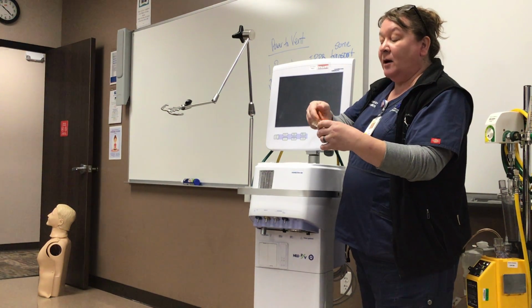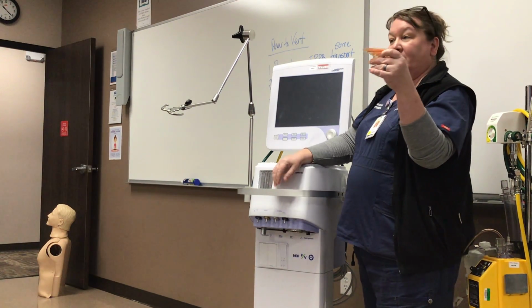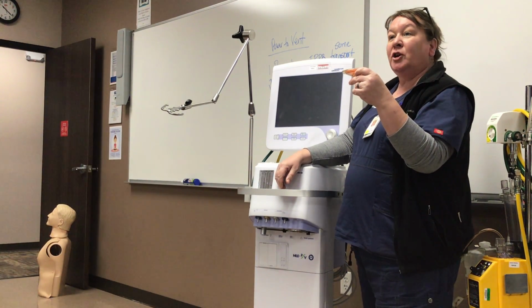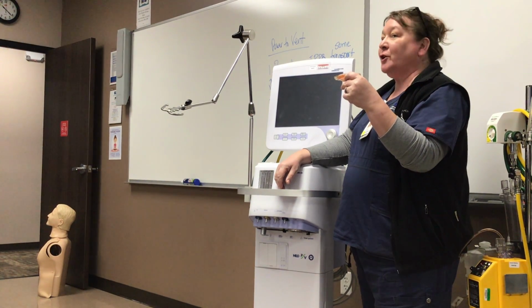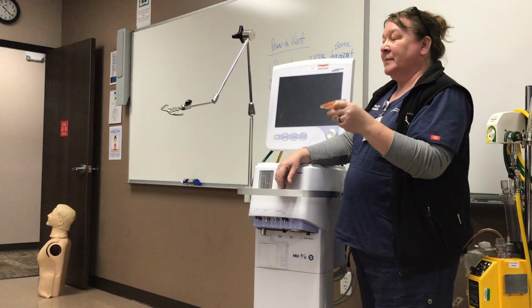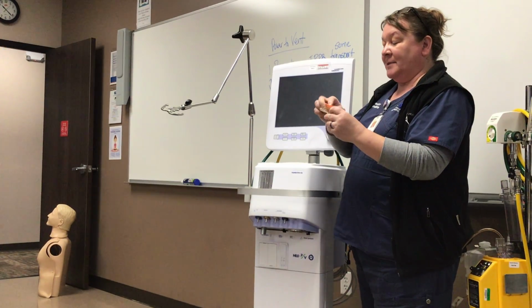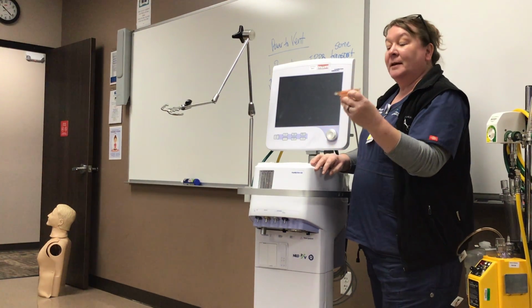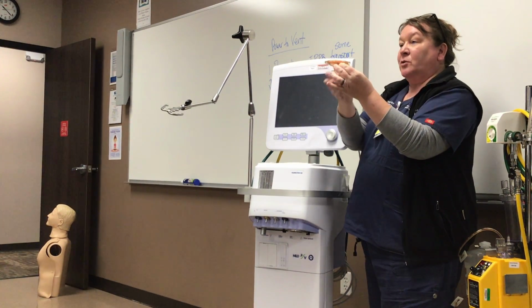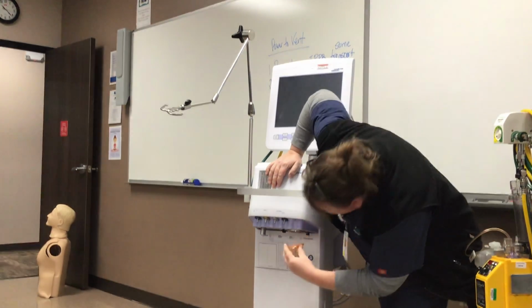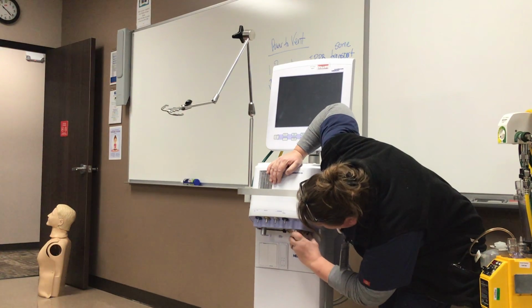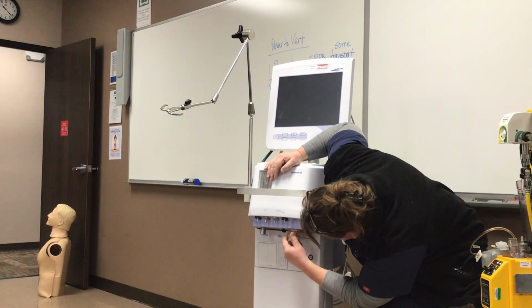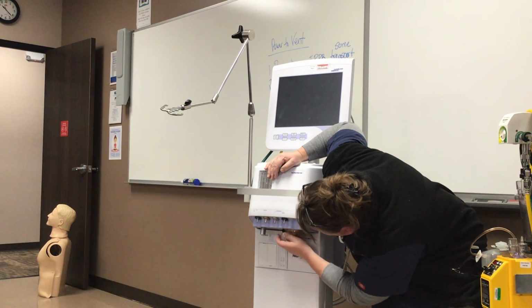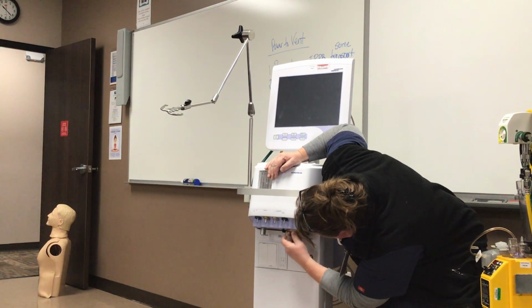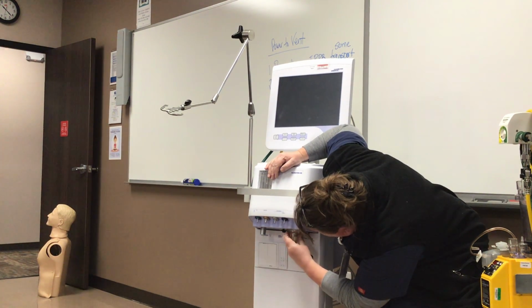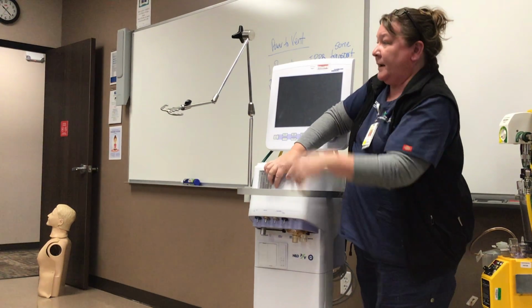If this is flipped upside down, the vent won't work, and I've also discovered that it will mess with your PEEP. So your PEEP reading is off, and you cannot figure out why. It's because this exhalation valve is in wrong. So keep it in mind. It's sometimes a little troubleshooting thing, so maybe you'll see it someday. Your expiratory side is always going to go onto here. And this is going to go back in, and you have to lock it into place. There's a little tab, so if you don't get it quite right, you have to twist it so that the tab locks it into place. That's still not quite right. There we go. So the tab is going to lock it into place now.